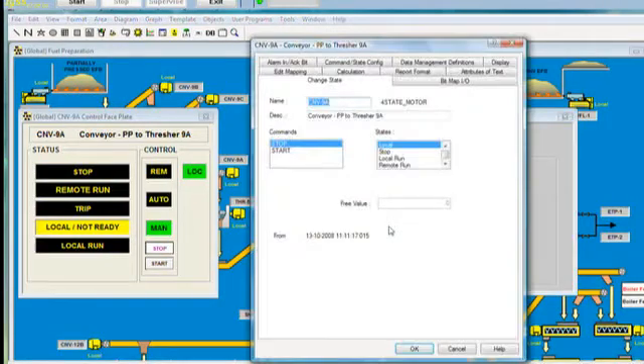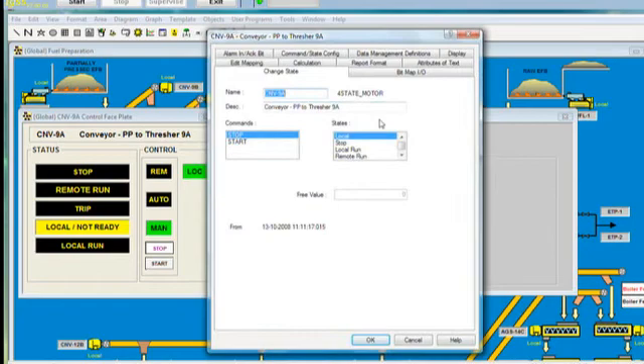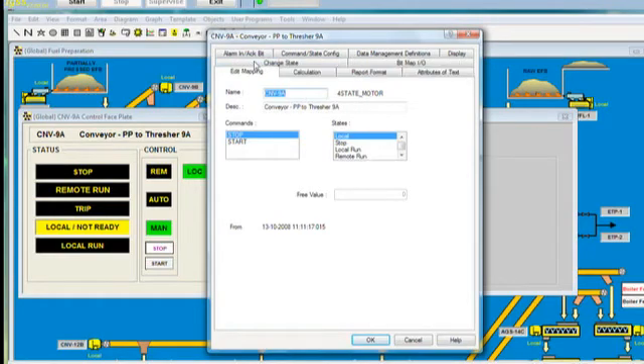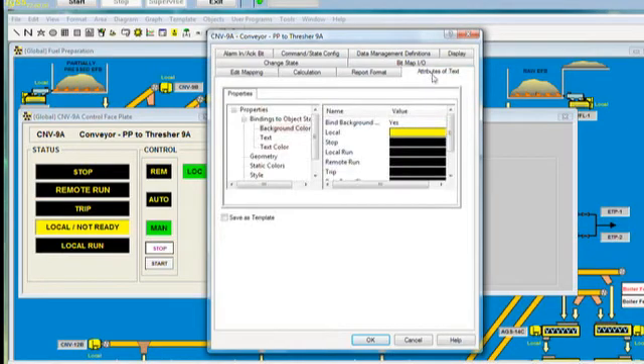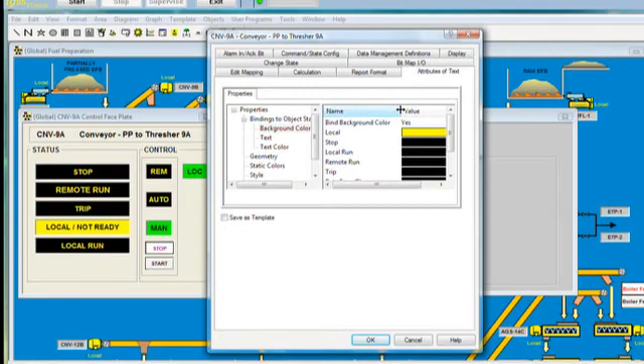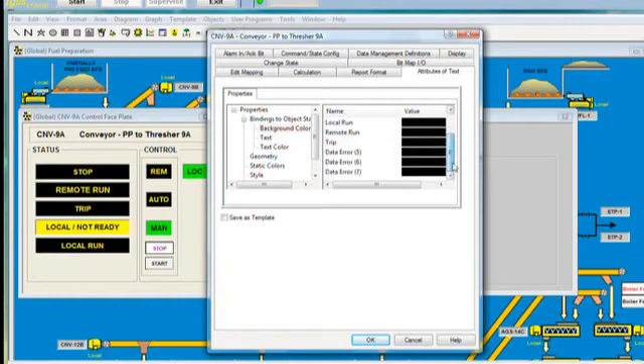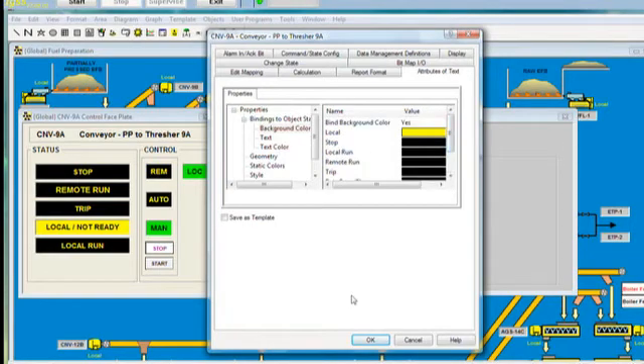Let's go inside the object to see how this was actually done, because this object is linked to the CNV9A object. We double-click it and can see that it's linked to the motor. The four-state motor is the template name. On the edit mapping tab we can see all the PLC addresses and how it was mapped into the PLC logic. If we go to the attributes of text tab, we can see how we connected the background color of the button to the actual state of the process component. When it's in local mode it will be yellow; all other states will turn black in this mode. That's how we created this effect on the screen.